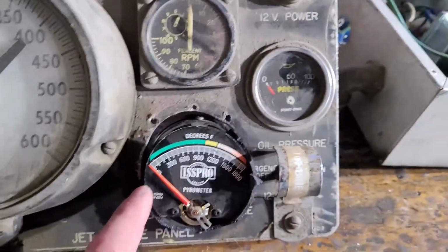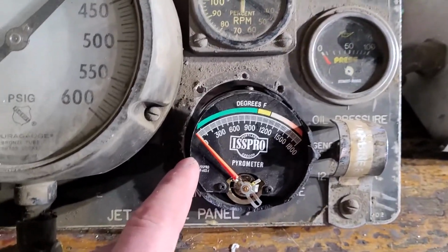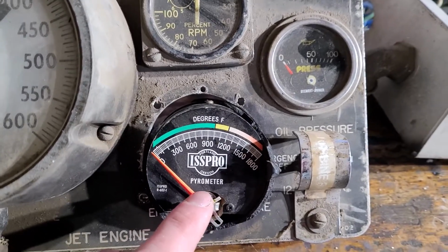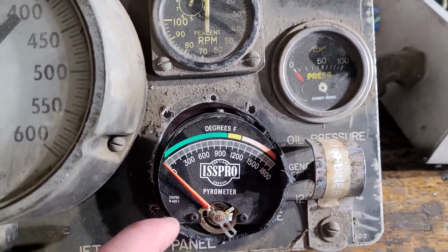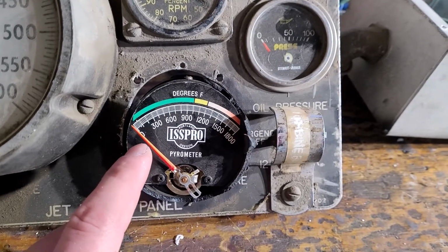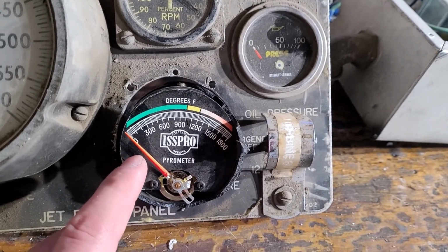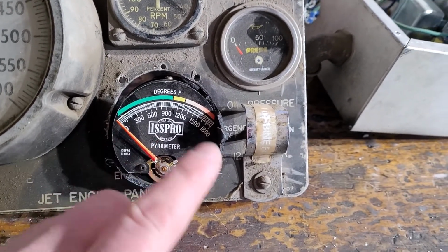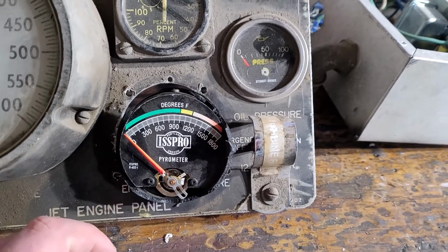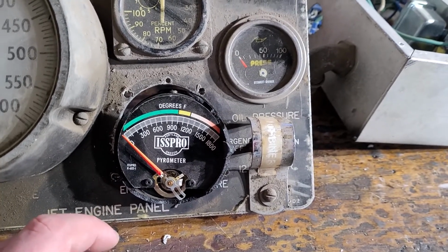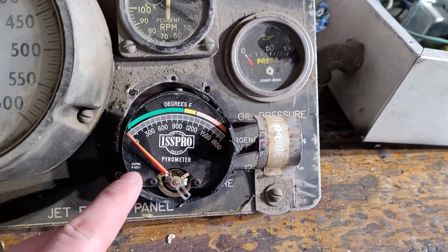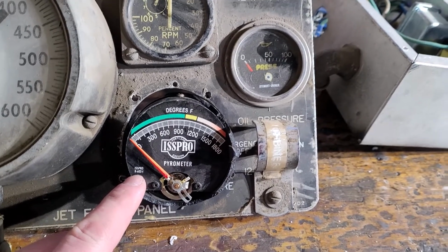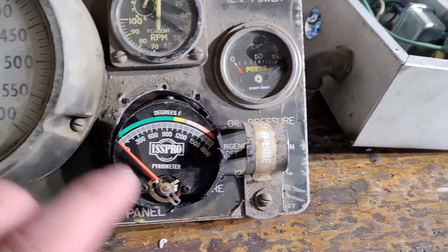So we'll see. This is the pyrometer, basically our exhaust gas temperatures. On this engine there's a handful of thermocouples, and we can test those with our meter to make sure they're working properly. There's a bunch of thermocouples on the back of the exhaust combustion chamber that are wired up, so those will just need to make their way back to this sensor.